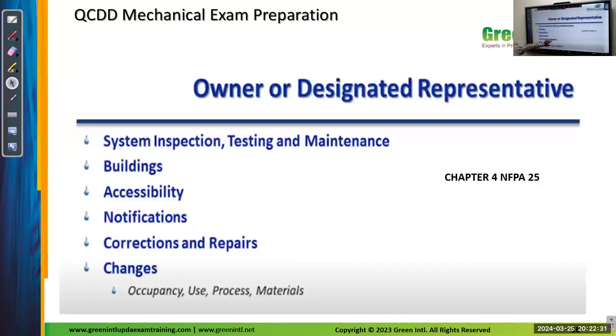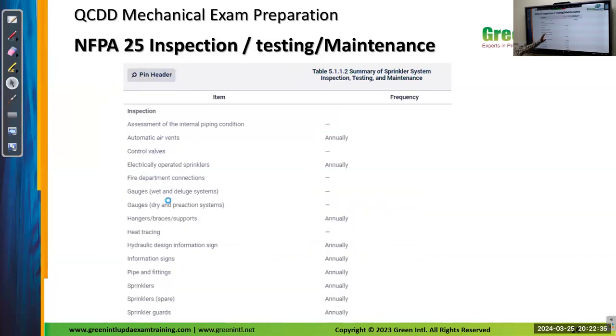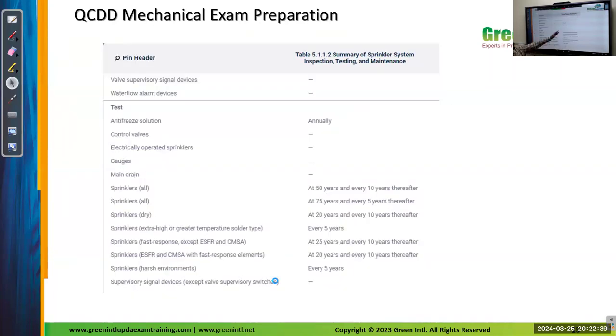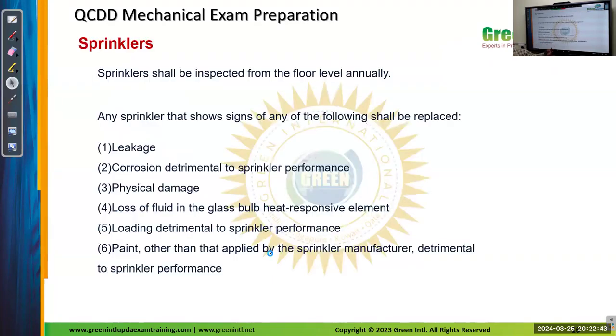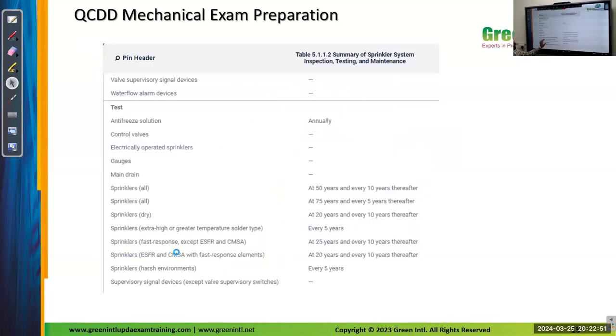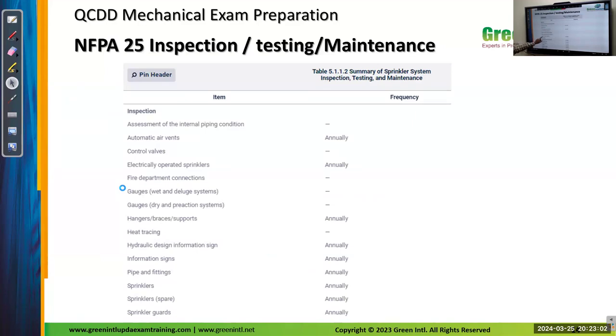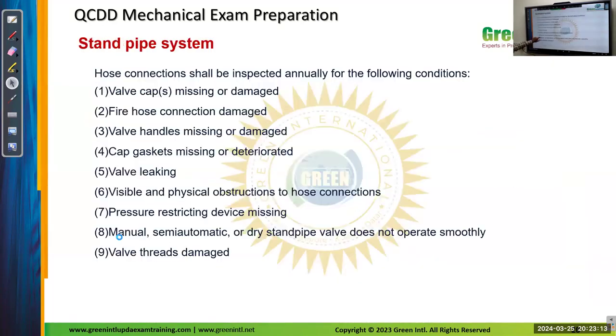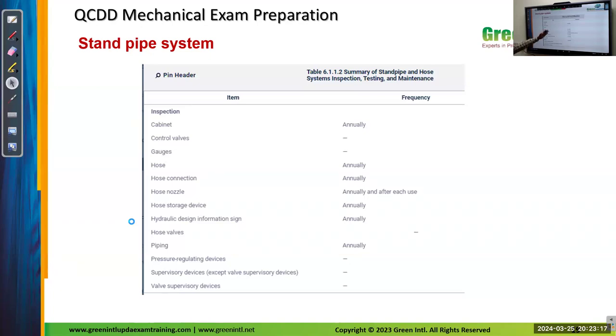From the NFPA, you can see the tables. Like this, there are plenty of tables. It will tell you whether it is annually or every 5 years or every 10 years or semi-annually, monthly, weekly. There are many tables. I just included 2 or 3. From that, you can find whether it is for sprinklers, all types of sprinklers. So this is for sprinkler systems and control valves, hangers. So this is for inspection testing frequency. And if you go into more detail, there are standpipes and hose systems. These items you can get from NFPA 14 as well. Okay.